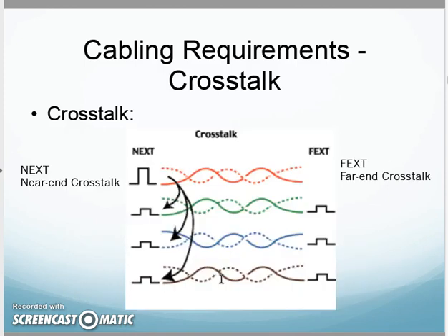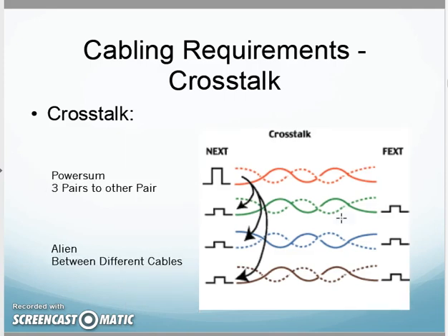So just to kind of further add to this, because they only briefly mention crosstalk, let me give you just a scotch more info here, because you're going to see this again when we start testing our cabling. There is such a thing as near-end crosstalk and far-end crosstalk. Well, don't let that throw you. Near-end crosstalk is, when you're testing this end, if I hook my meter here, testing at the near end of the cable. Far-end crosstalk would be away from you, the far end of the cable run. Okay? So don't let that fool you or confuse you, if you will. That's what they're getting at with near-end and far-end.